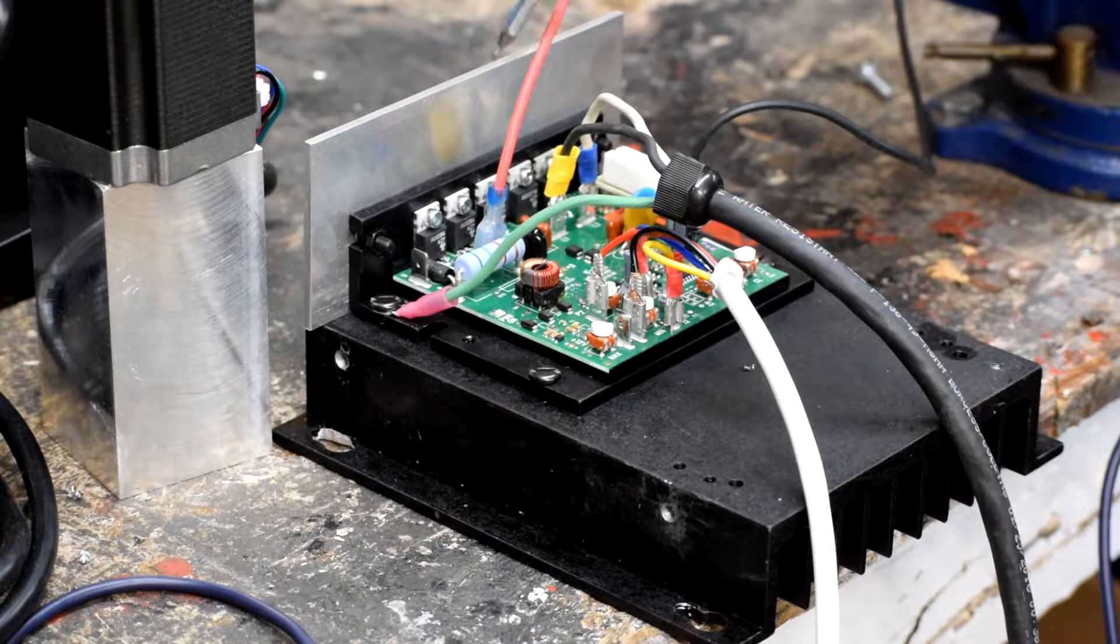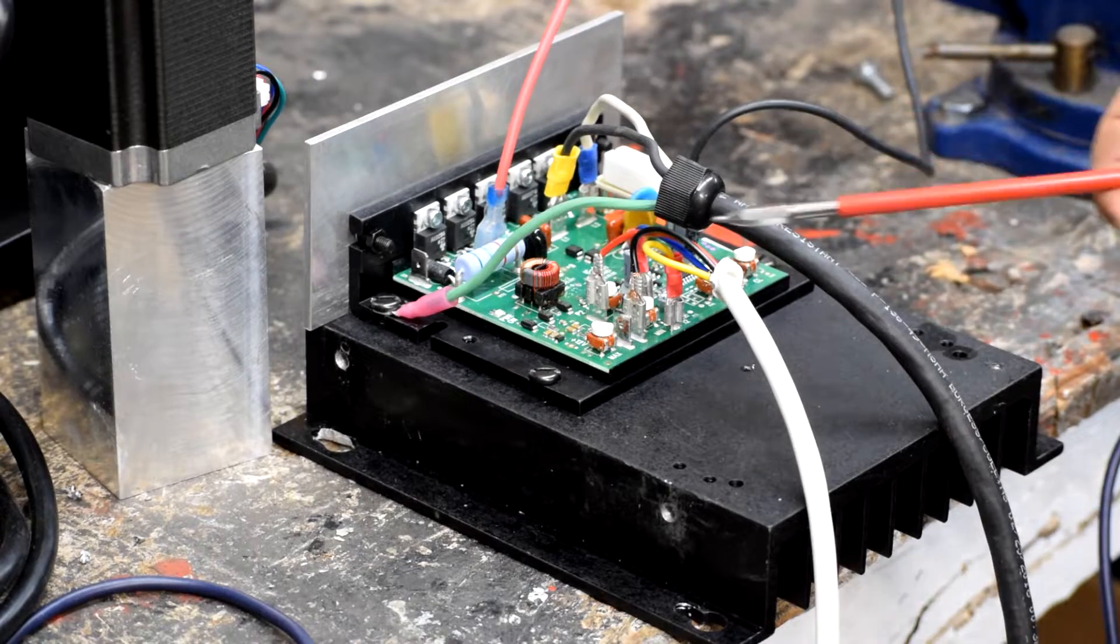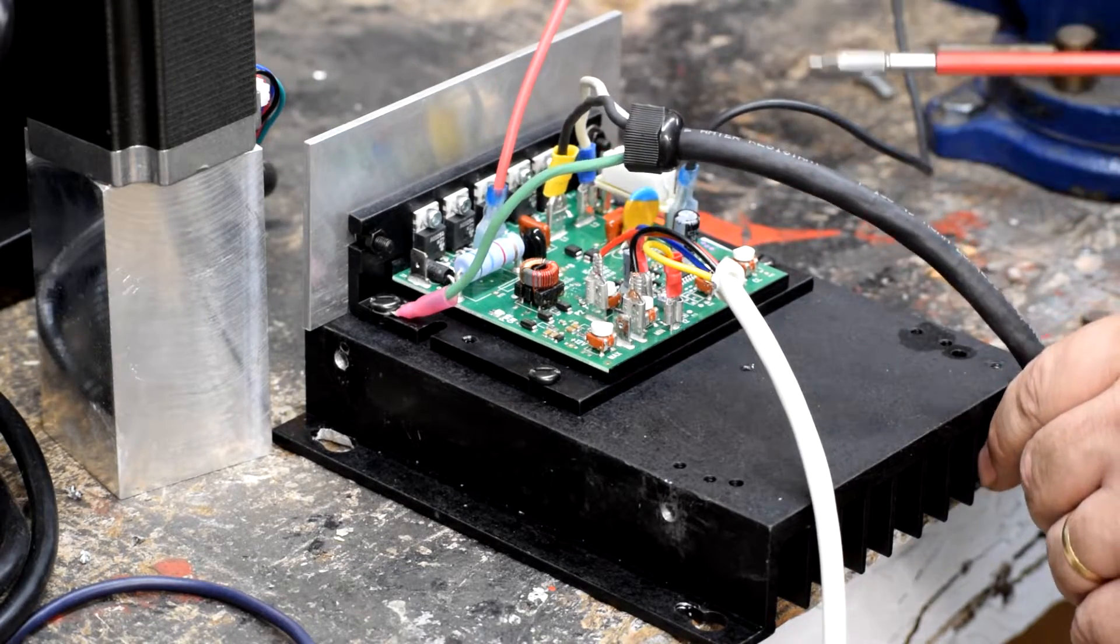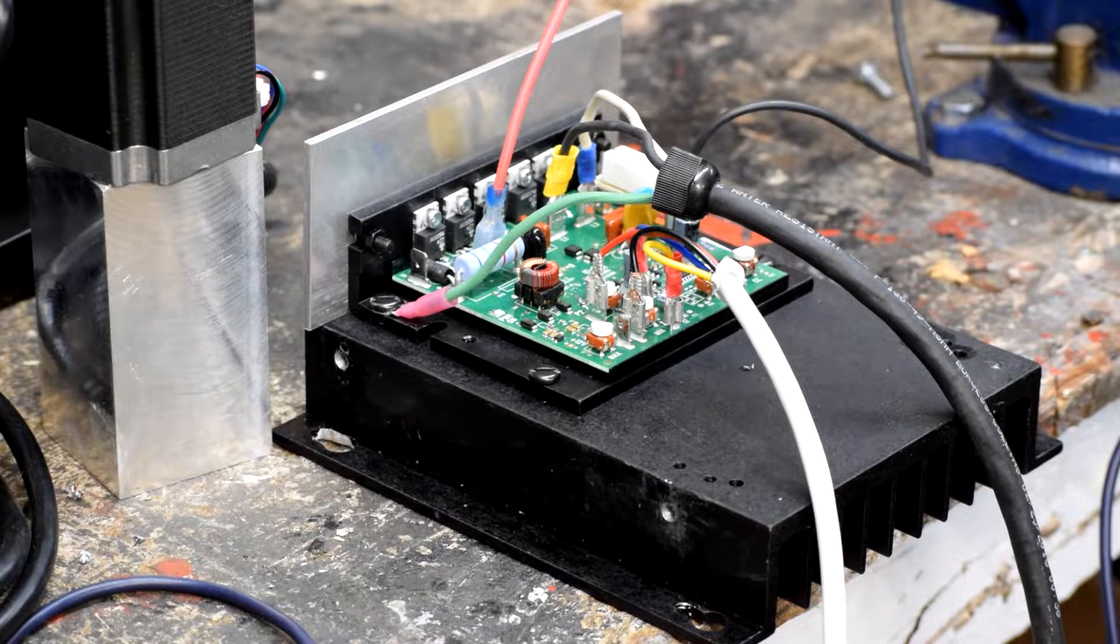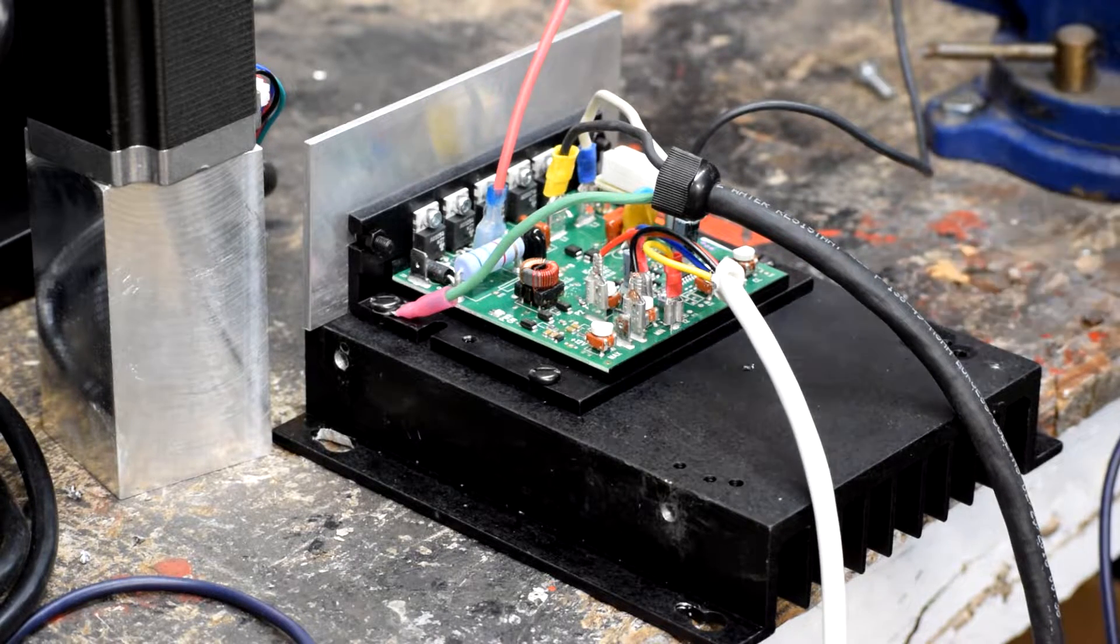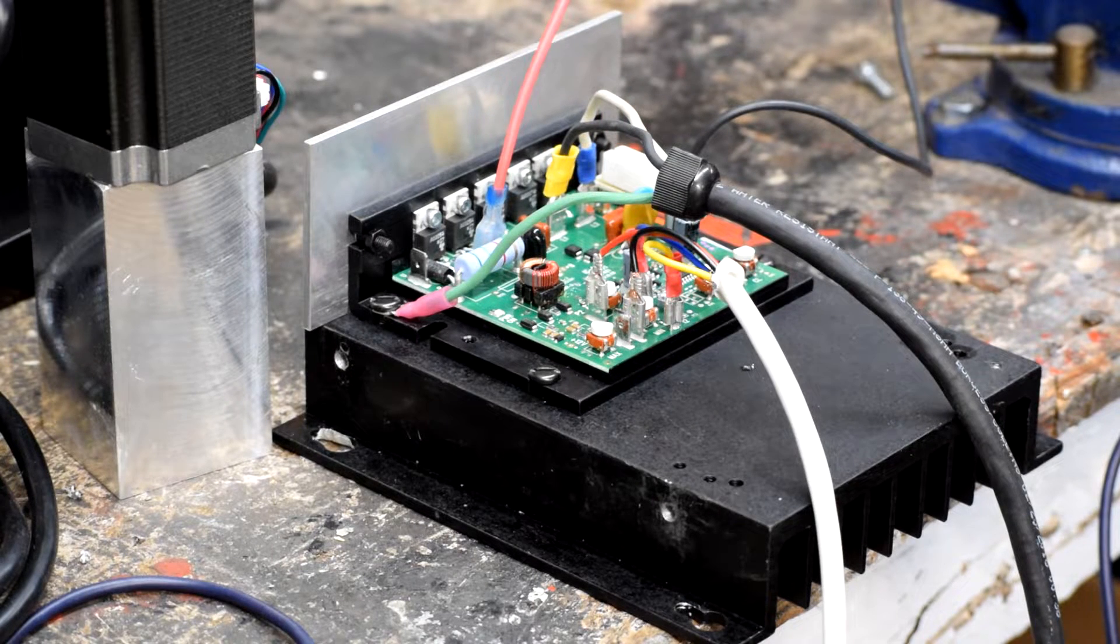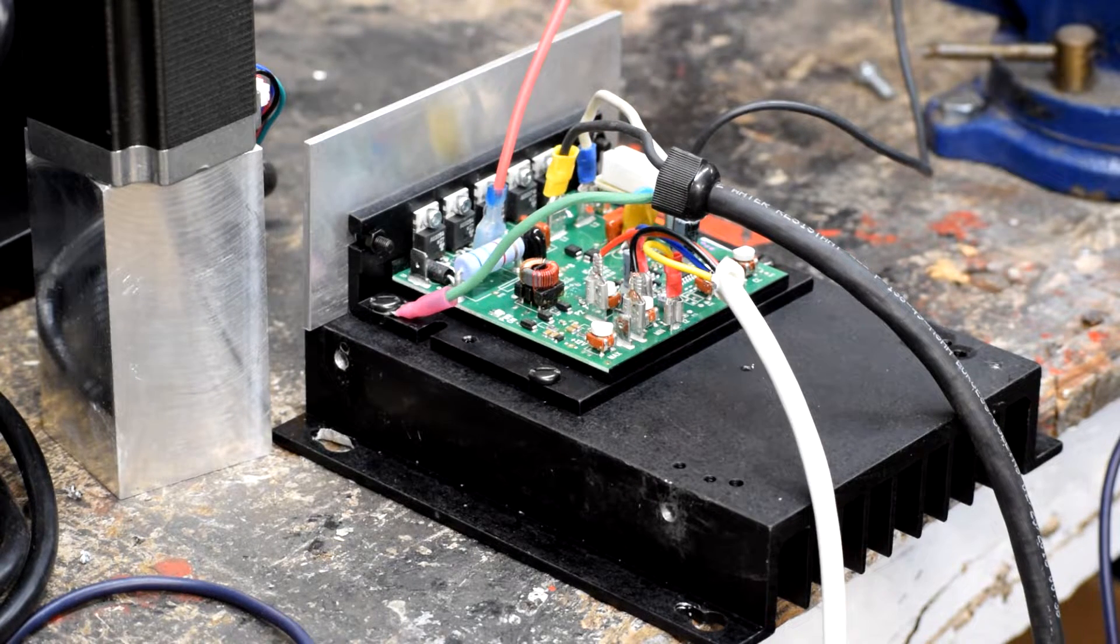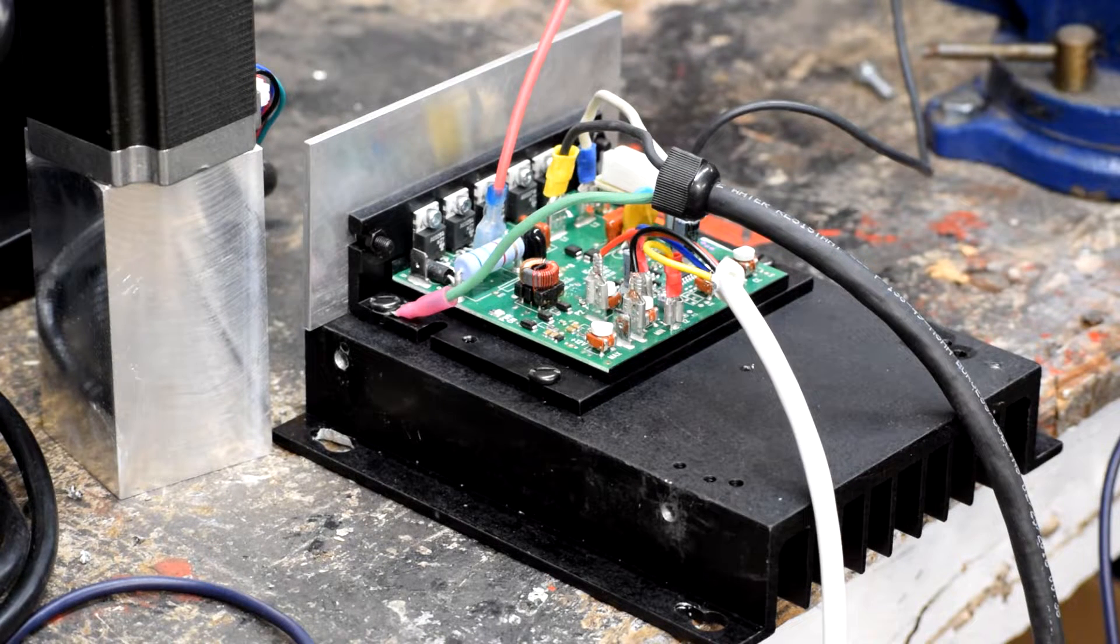This is the DC motor plus lead. This is the DC motor negative lead. AC comes in here. A varying voltage signal comes across this to tell how much to go out, and it just varies the signal out here to control the speed of the DC motor. Very, very simple. And then it has a few of these little pots on here to allow you to change for acceleration and maximums and minimums, and just kind of fine-tune the controller so that it works for your motor. A very simple component. Not much to it.